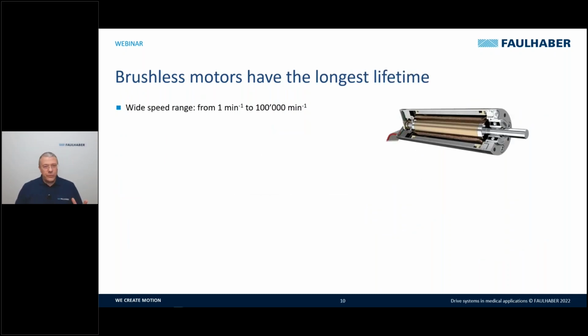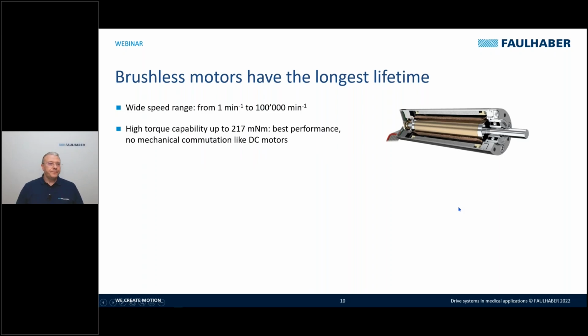Another motor technology is the brushless motor technology. They have the longest lifetime, and they can achieve the highest speed, up to 100,000 RPM for several medical applications. They have the possibility to develop high torque. The larger motors cannot reach 100,000 RPM, but they can deliver higher torque. There is no mechanical commutation like in a DC motor, because we have electronic commutation.